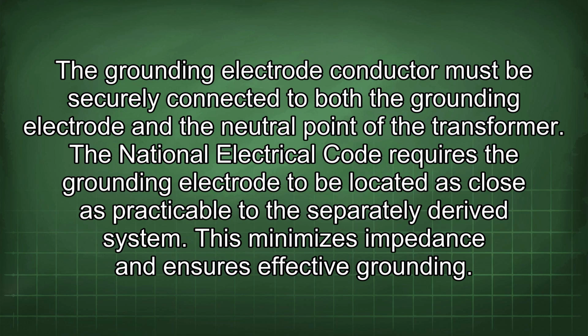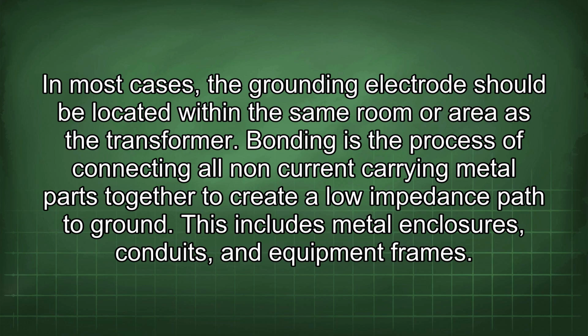The National Electrical Code requires the grounding electrode to be located as close as practicable to the separately derived system. This minimizes impedance and ensures effective grounding. In most cases, the grounding electrode should be located within the same room or area as the transformer.